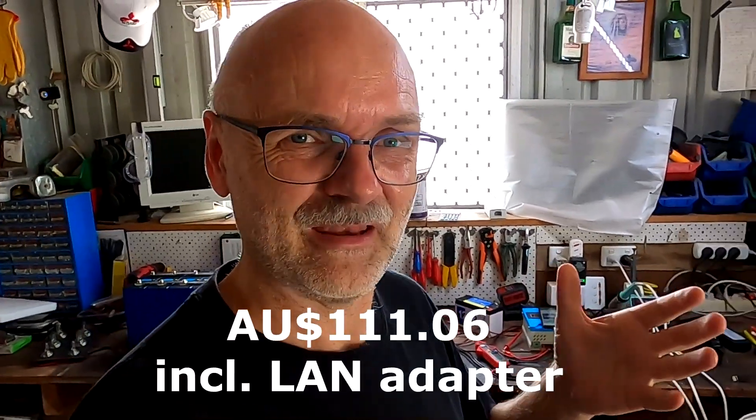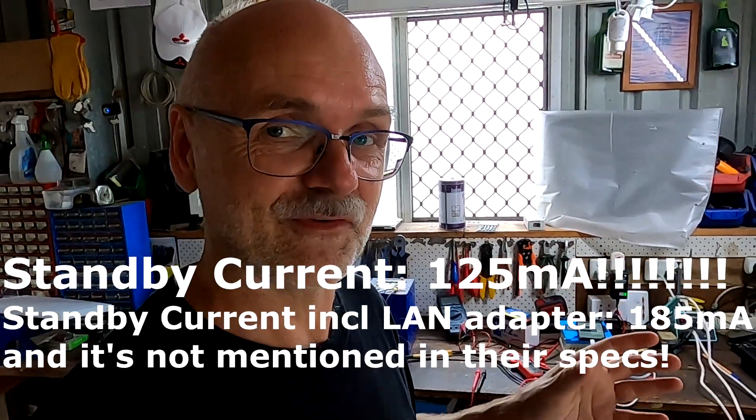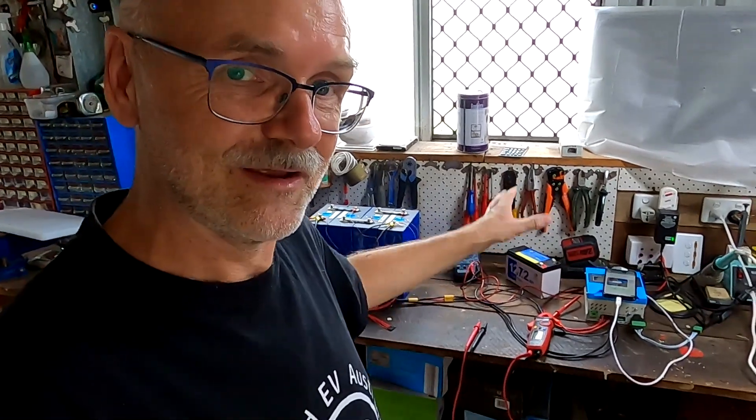The reason I bought this controller was first the price: 110–120 AUD including shipping from China for a 30A 48V MPPT charge controller, intended for my 1200W solar panel strings. Another positive is the three-year warranty — three times more than anyone else on AliExpress offers. But then I found one spec I missed on the website: the standby current is 125 milliamps. I verified with a clamp meter and a multimeter in-line — it's 125mA. That's far too much.